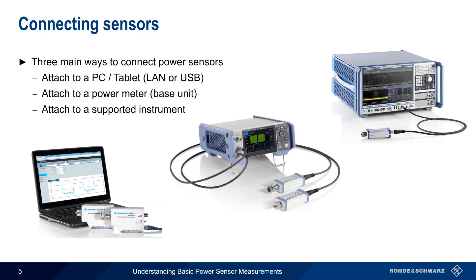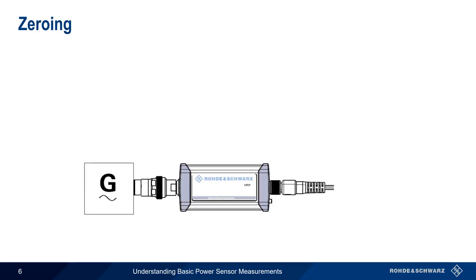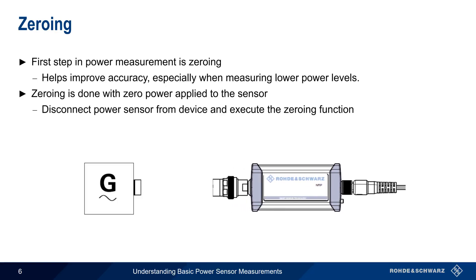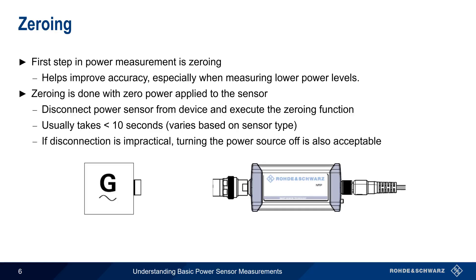No matter which way we interface to the sensor, the basic measurement procedure and results are the same. After we're sure that our sensor is properly connected to our PC, power meter, or instrument, the first step in any power measurement is something called zeroing. Zeroing helps to improve accuracy and ensure the validity of our measurement result, especially when we're measuring lower power levels. Zeroing is done with zero power applied to the sensor — this means physically disconnecting the power sensor from the device under test and then executing the zeroing function. This usually takes less than 10 seconds, but will vary based on the sensor type. Although zeroing should be done with the sensor physically disconnected, in many cases this is impractical, in which case turning off the power source is an acceptable alternative. Note also that many sensors will automatically abort the measurement if you try to zero them with power still on.